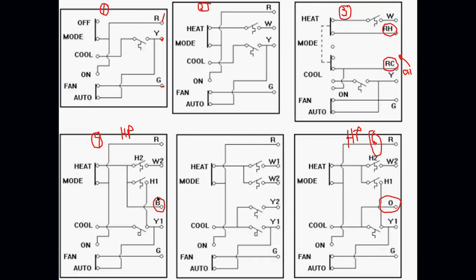And you can see where that wire coming out of the terminal goes to. In number 4, that wire goes up, and it's energized when my mode is in heating, if you look at this down here through, okay? In number 6, you follow that terminal down, and it's energized when my mode is in cooling.